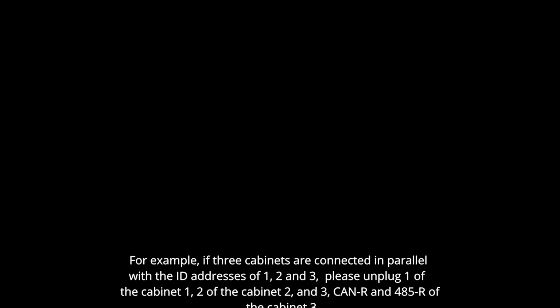For example, if 3 cabinets are connected in parallel with the ID addresses of 1, 2 and 3, please unplug one of the cabinet 1, 2 of the cabinet 2, and 3, CAN-R and 485-R of the cabinet 3. If 4 cabinets are connected in parallel with the ID addresses of 1, 2, 3, and 4, please unplug one of the cabinet 1, 2 of the cabinet 2, 3 of the cabinet 3, and 4, CAN-R and 485-R of the cabinet 4. There is no need to unplug the GBMS.